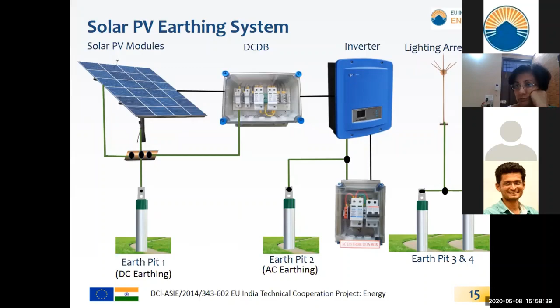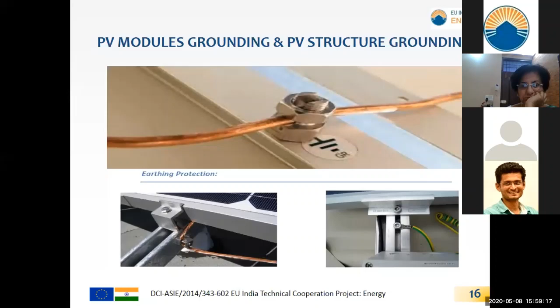So here you can see structure earthing and the PV module earthing. Normally we all do the structure earthing, but in solar PV rooftop and ground mounted systems, it is compulsory to earth each and every solar module, because the frame of the solar module is anodized aluminum, and anodized aluminum acts as an insulator. So you have to connect each and every panel through bonding, and then connect it to the grounding or to the structure.